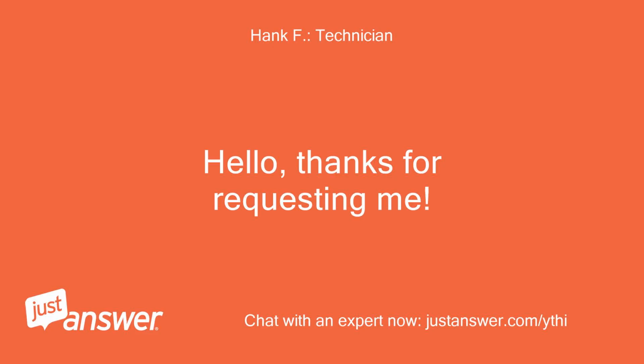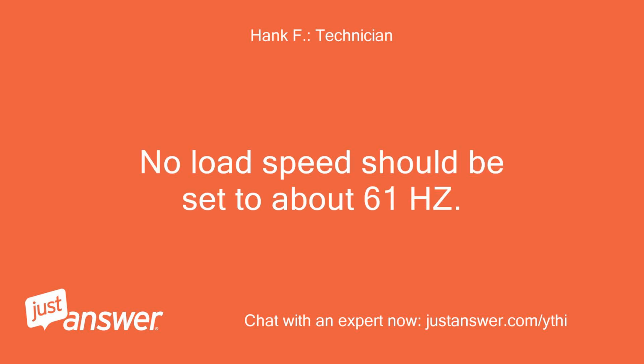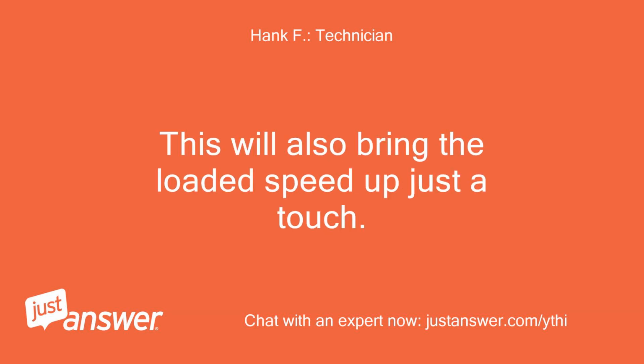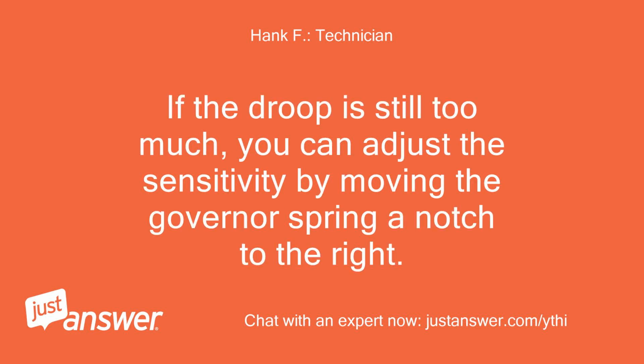Hello, thanks for requesting me. No load speed should be set to about 61 Hz. This will also bring the loaded speed up just a touch. If the droop is still too much, you can adjust the sensitivity by moving the governor spring a notch to the right.